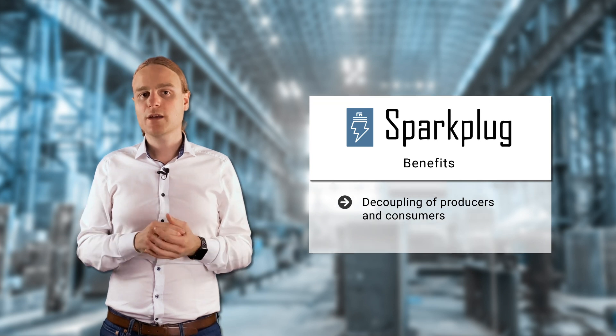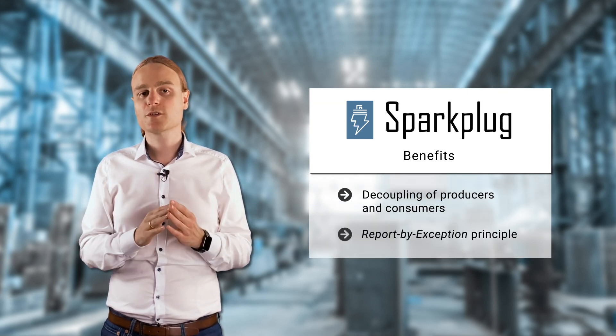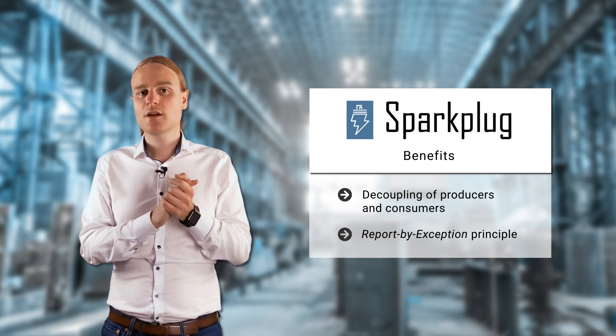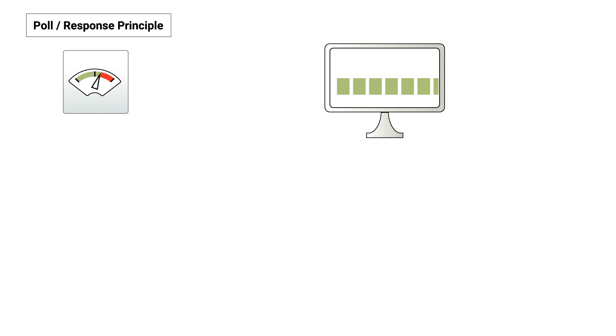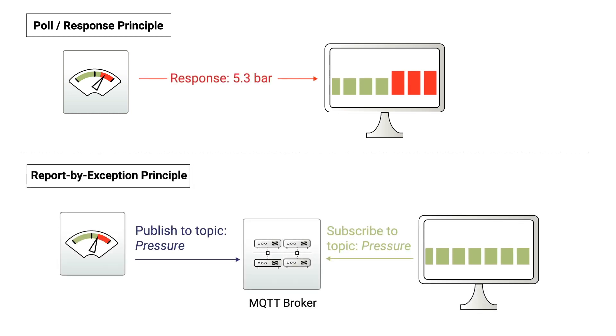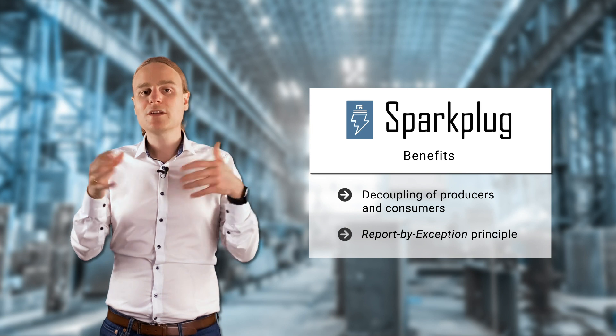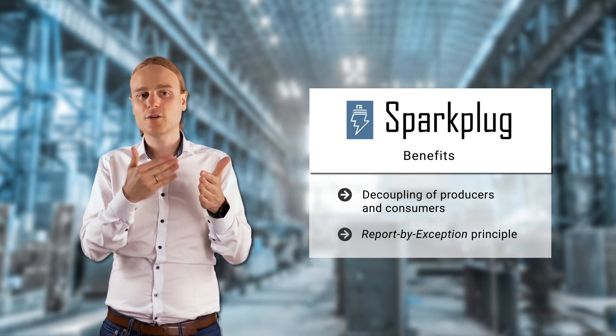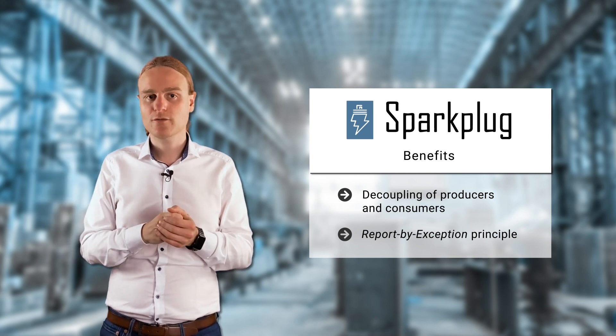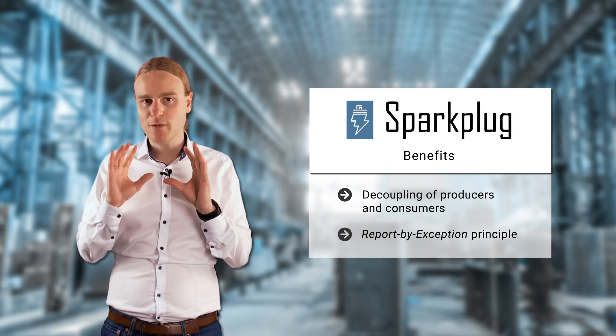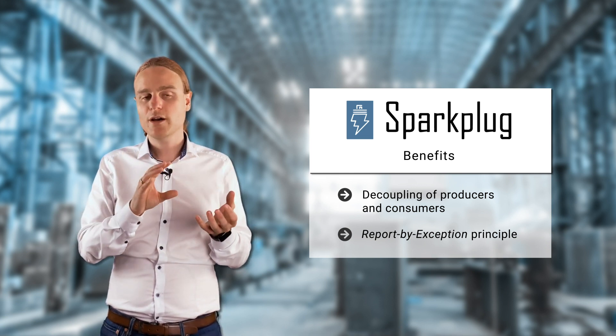Then we have the report-by-exception principle. This is quite different from a poll-response principle, because data is only reported if it changes. With a traditional architecture, a pressure sensor would be polled once per second or even more often, even if the data doesn't change. With Sparkplug, data is only published when it changes. The same is true for state changes — if a device goes online or offline, this is published immediately. You get things in near real-time, and report-by-exception saves you bandwidth, computing power, and memory consumption on your devices, producers, and consumers.